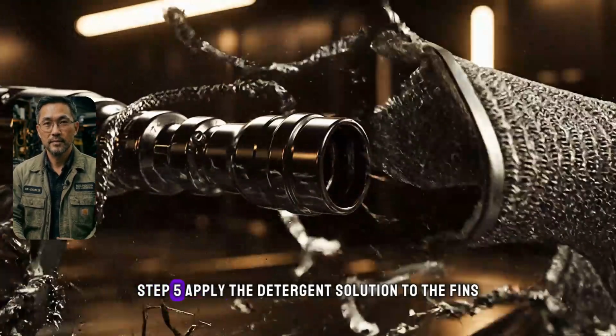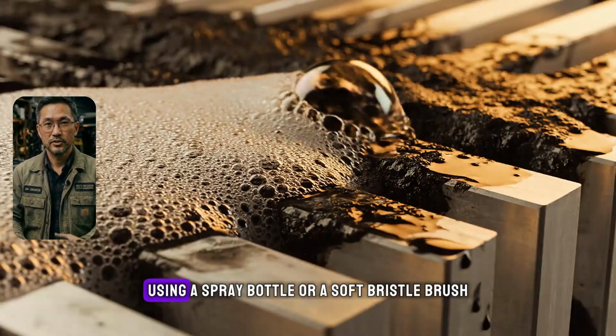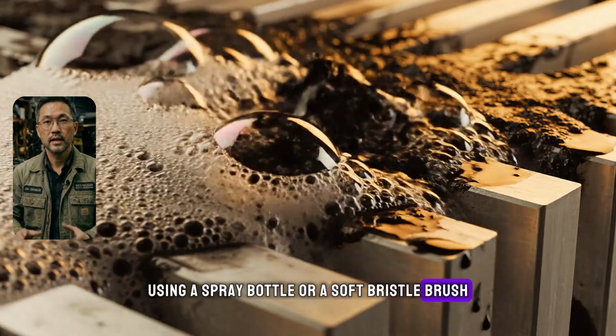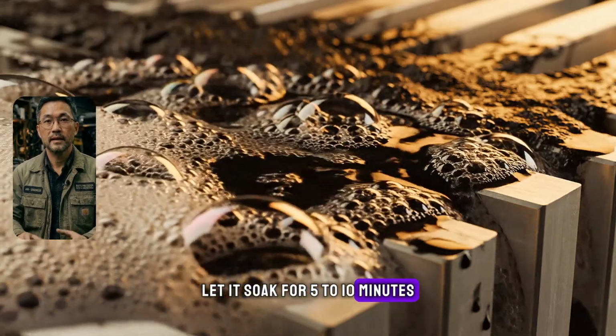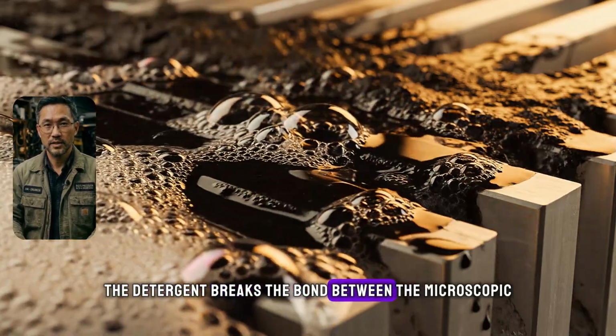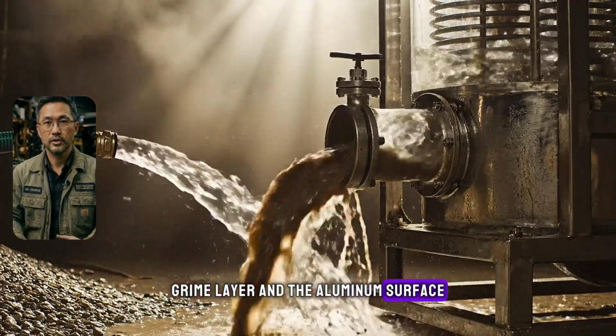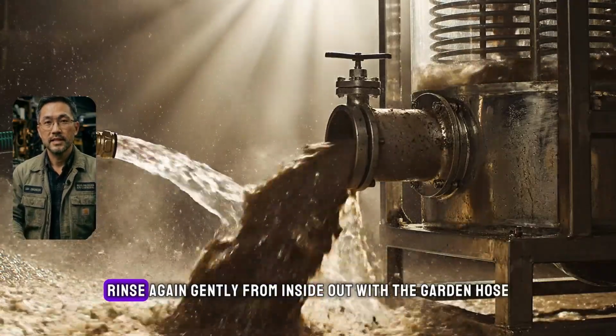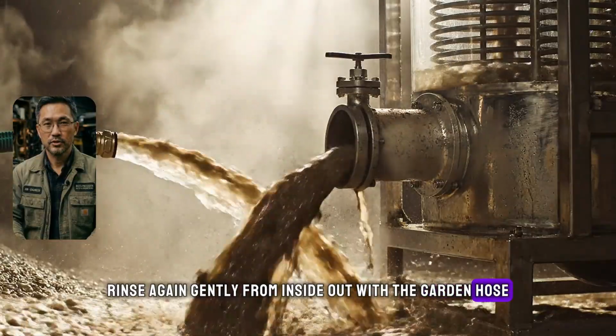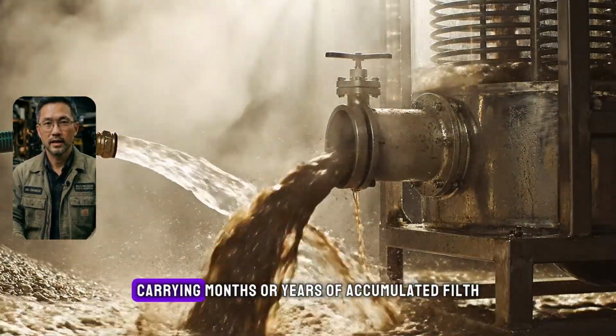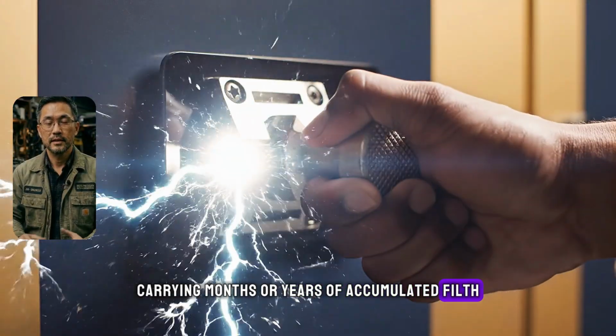Step 5. Apply the detergent solution to the fins using a spray bottle or a soft bristle brush. Let it soak for 5 to 10 minutes. The detergent breaks the bond between the microscopic grime layer and the aluminum surface. Step 6. Rinse again gently from inside out with the garden hose. You will see dirty water flowing out, carrying months or years of accumulated filth.